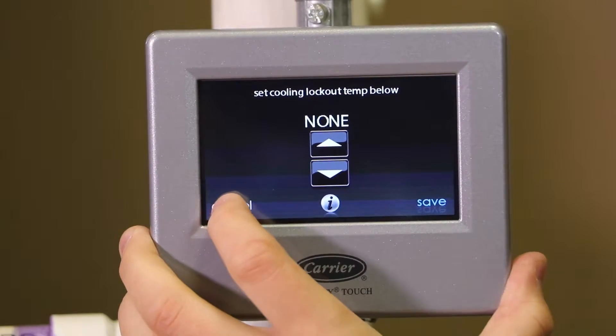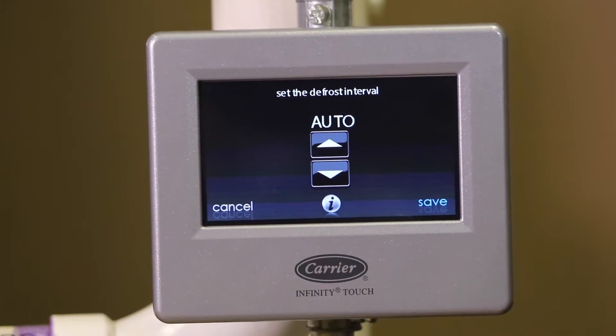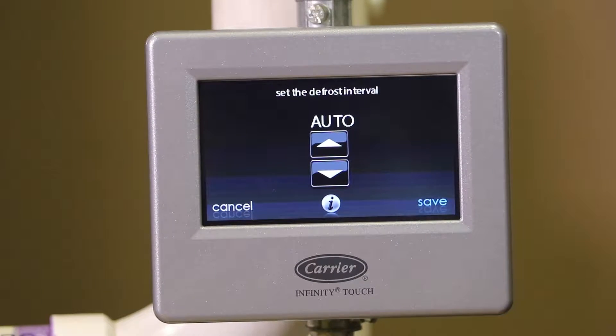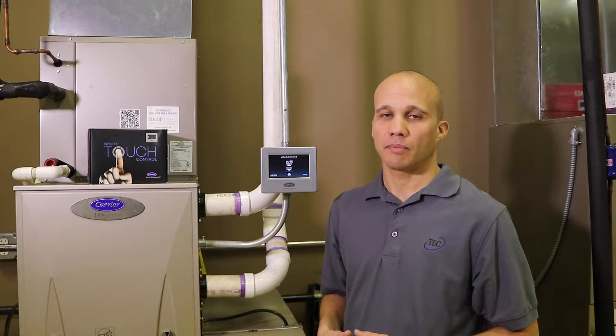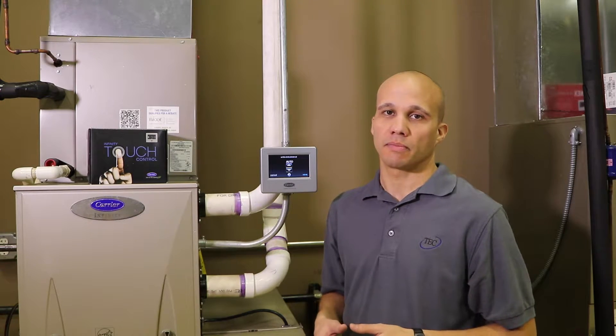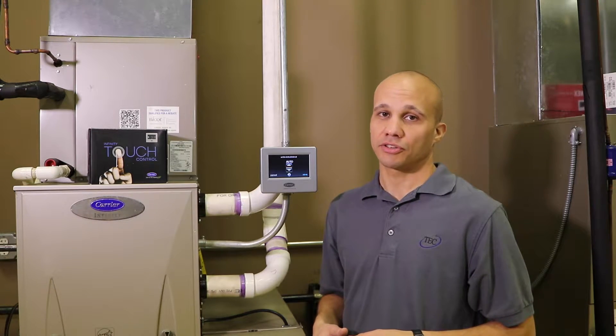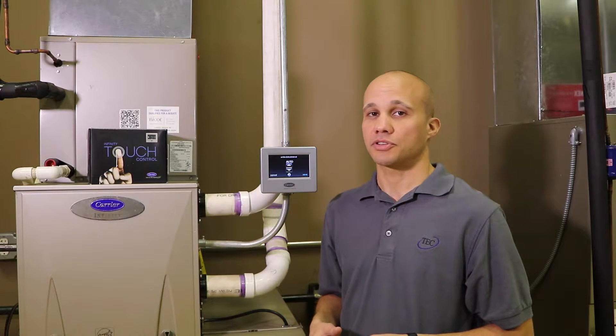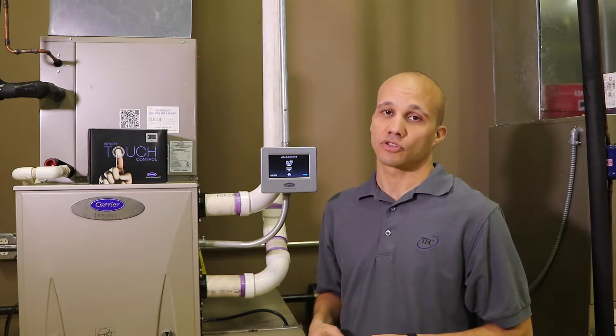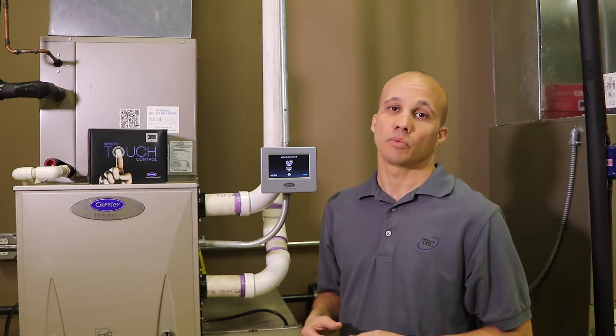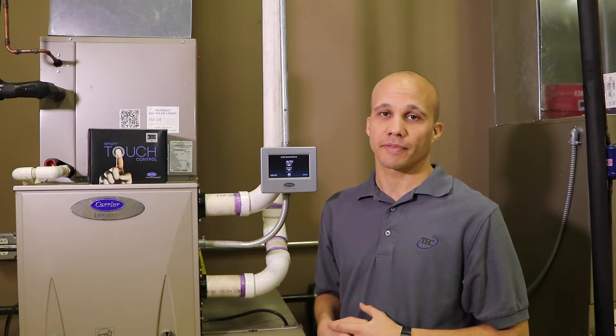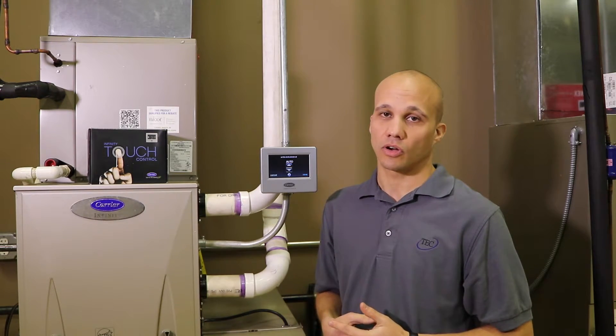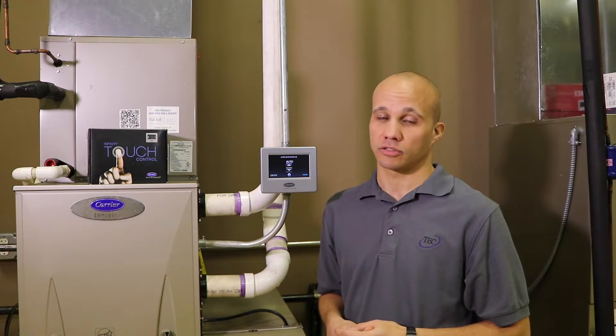Next is defrost interval. Because we have a heat pump we have this screen. By default it has auto defrost, which is a very nice feature. Instead of being a traditional heat pump where we change into defrost mode every so many minutes, this will do it only if we absolutely have to. That particular unit has a saturated condensing temperature sensor and an outdoor air temperature sensor. It knows when those two things are getting close to each other near freezing temperature, and will go into defrost mode — temporarily switching to cooling mode to use the warm air from the house to thaw the outdoor coil, which temporarily discharges cool air into the home. We want to minimize that, so we let the auto mode do its thing.